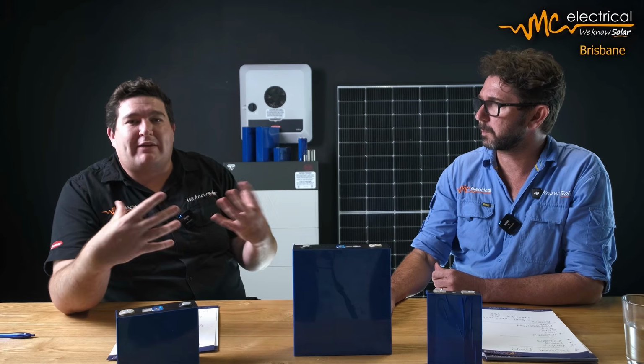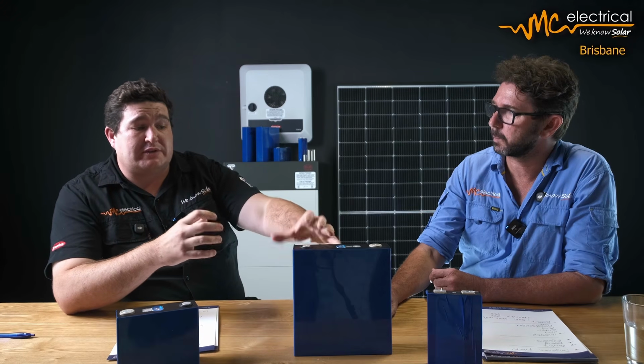When we're looking at industrial size battery systems, like 5 megawatt hour packs used for a solar farm, these are actively cooled with liquid cooling. There's refrigerants in them, really trying to suck a lot of the heat out of these battery packs, and it's hard to do so because there's so much volume.